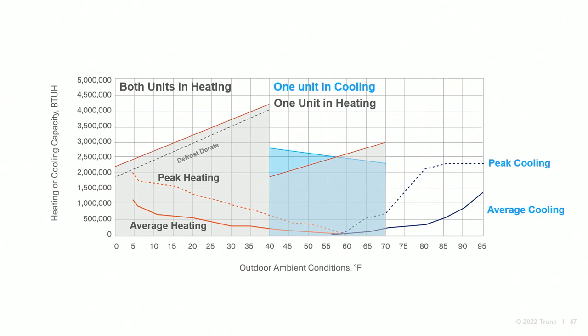Next, we're showing the cooling capacity between 40 and 70 degrees. Notice this time the capacity derate is opposite the heating capacity derate because we lose cooling capacity as the ambient increases. Above 70 degrees, both units are dedicated to cooling and have more than enough capacity to meet the building loads. Across the board, you can see there is no lack of capacity to meet the building loads, and the heat pumps will be lightly loaded for much of the year. To that point, let's take a look at the actual run hours for these two units.